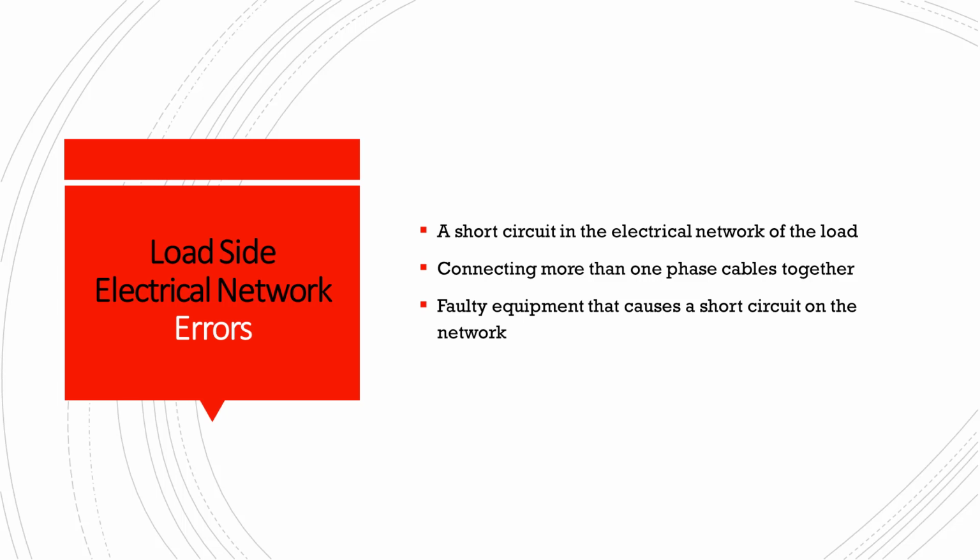We also realized that 2 minutes 30 seconds is usually the period when the compressors of AC units power up. So we concluded that the compressors of some AC units may be faulty, because not all the AC units we were using were inverter AC. Over time, at the end of all the troubleshooting, we realized that whether your AC units are inverter type or not, the solar system is going to carry them. So we had assumed initially that because they were not inverter type, the compressors were probably causing a short circuit on the network.